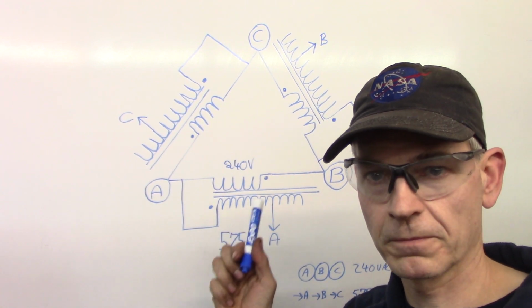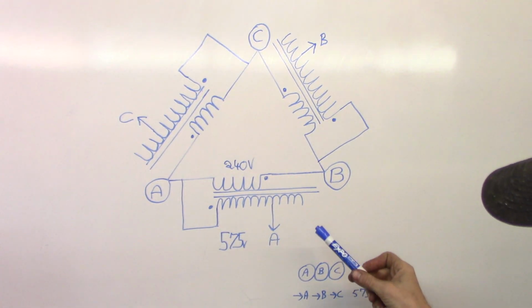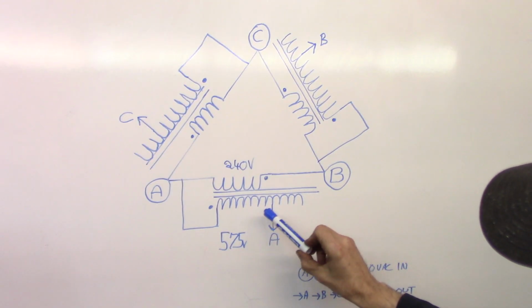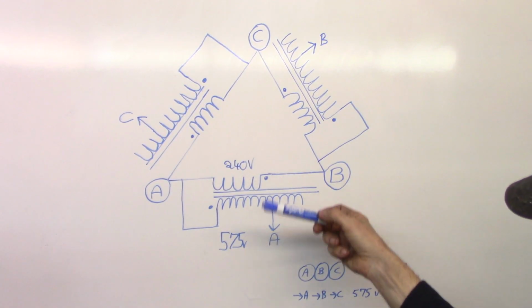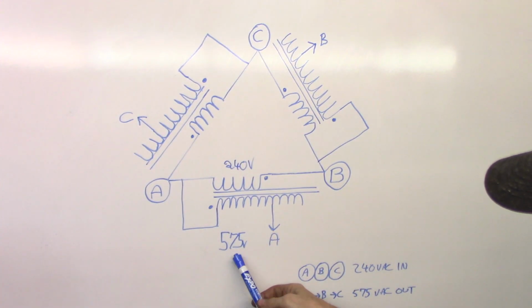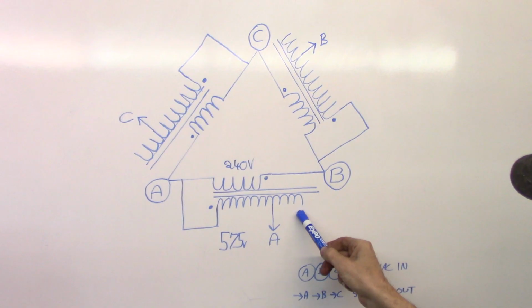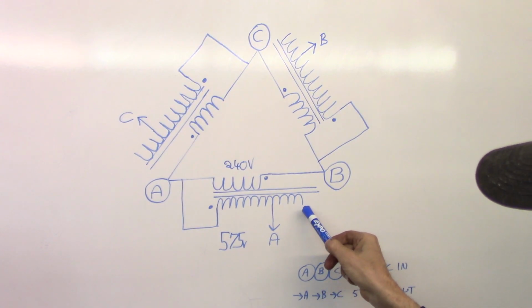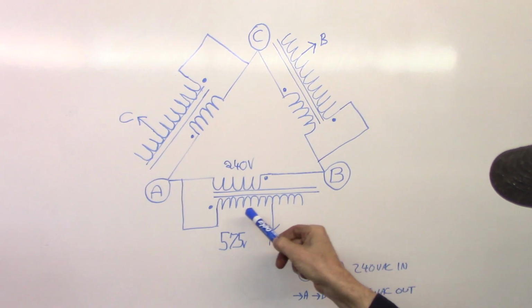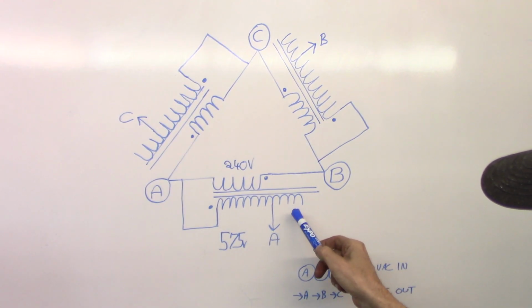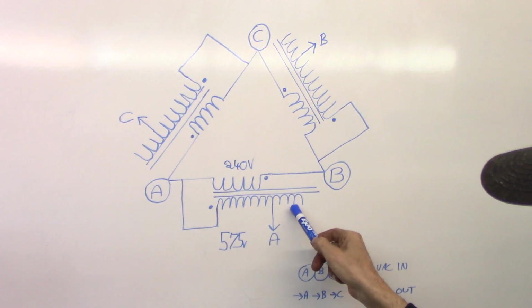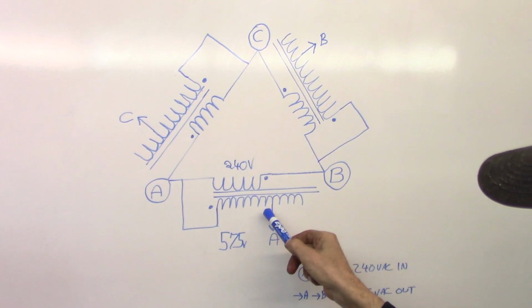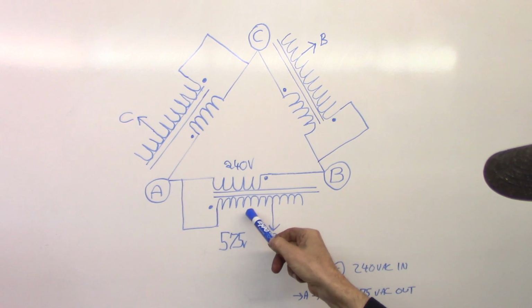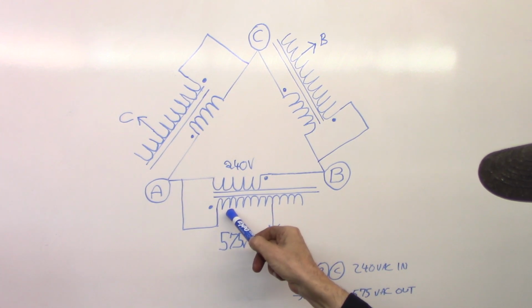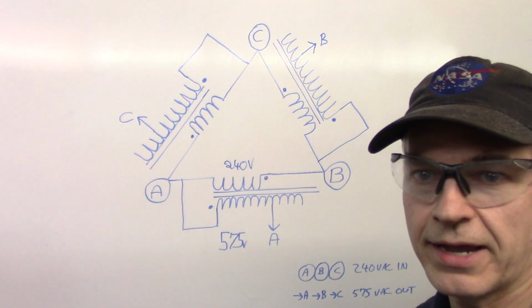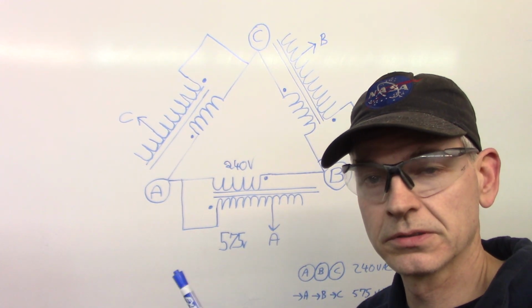It's normal, okay. So the secondary - it's confusing because I'm running them backwards and I say primary and secondary - the other side of the transformer is capable of like 600 and some volts. You got multiple taps, like 7 or 8 taps on there: 600 volts, 575, 550, 525, 480, 460, 440, 390, 380, 370. It's a whole bunch of taps. Very versatile transformer.